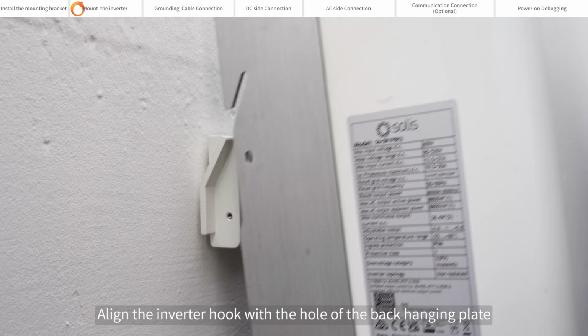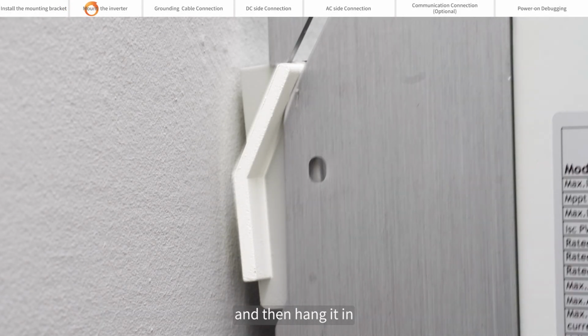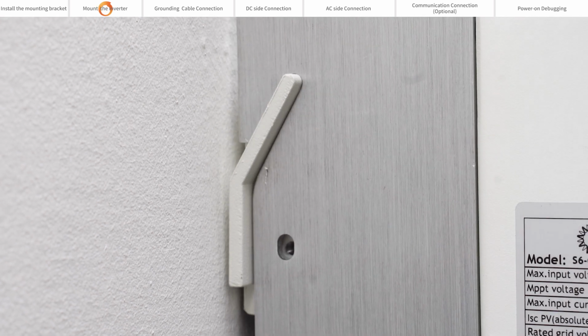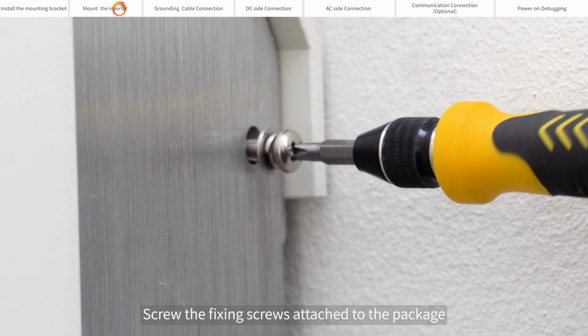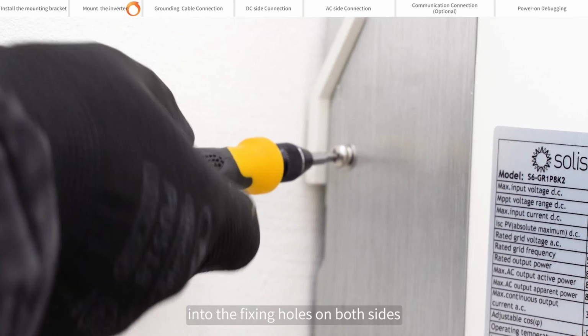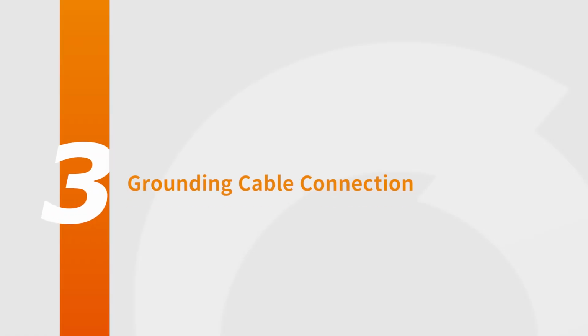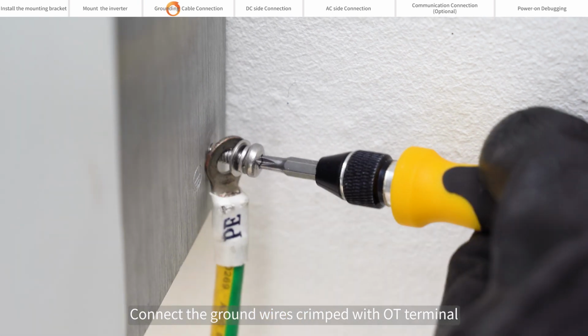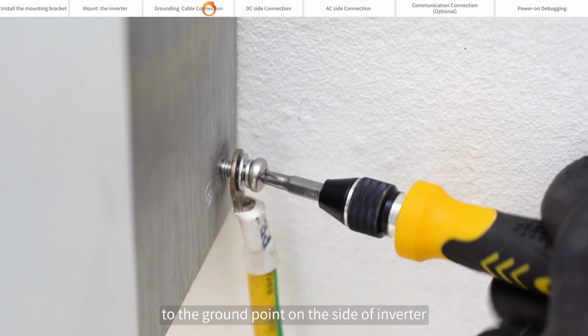Align the inverter hook with the hole of the back hanging plate and then hang it in. Screw the fixing screws attached to the package into the fixing holes on both sides. Connect the ground wires crimped with OT terminal to the ground point on the side of the inverter.